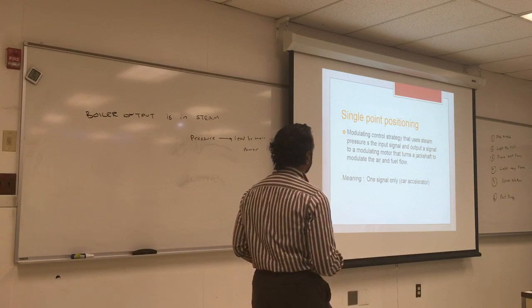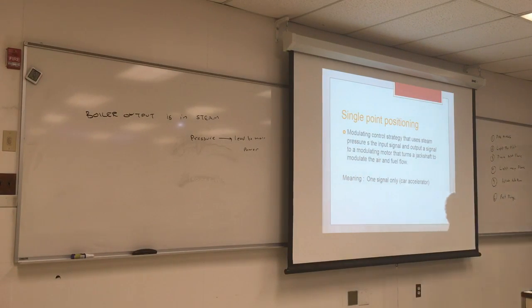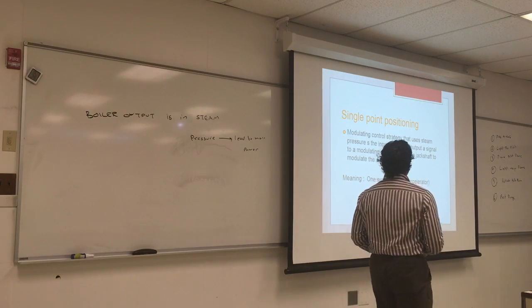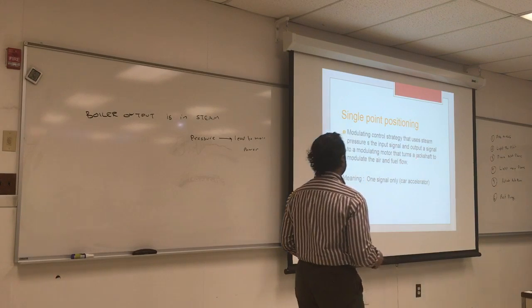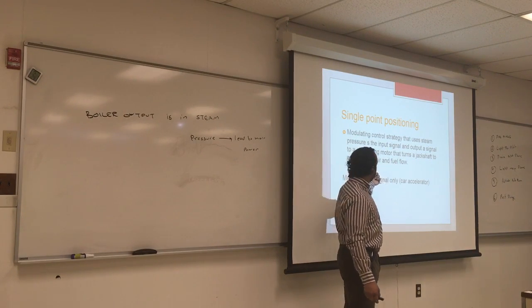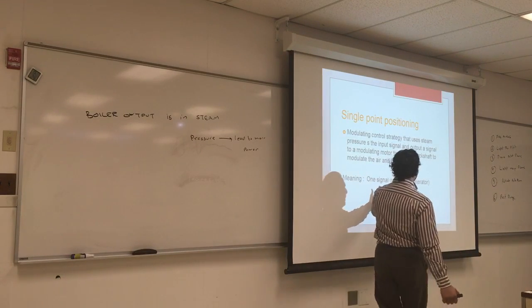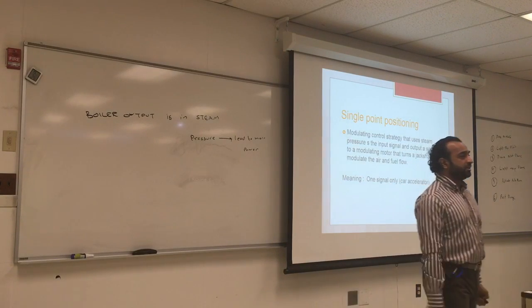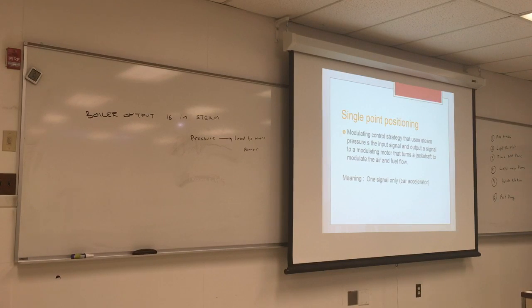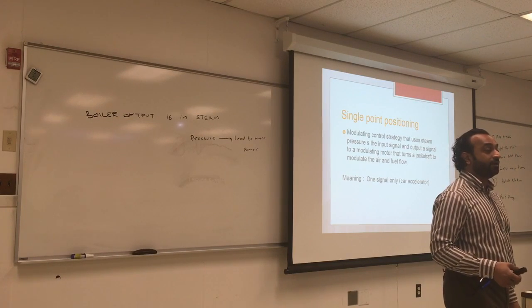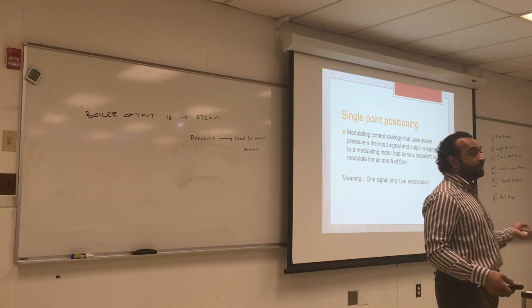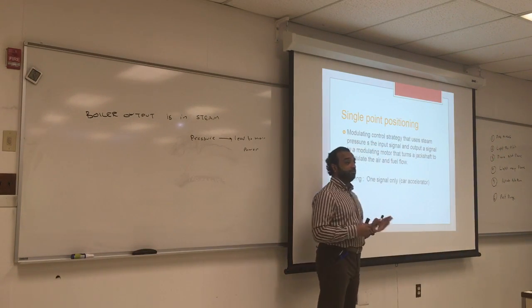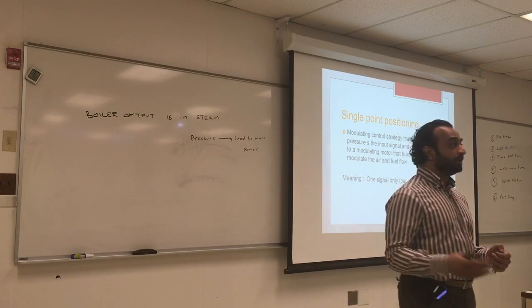There's something called single point positioning. It's a modulating system where the steam is the input signal and the output signal modulates a motor that turns a jackshaft to modulate the air and fuel flow. One signal only — like the car accelerator. You hit the gas and the engine will increase the fuel and also increase the air. So single point positioning means you only control the fuel coming in, and there is an automated system that will increase the air based on that fuel.